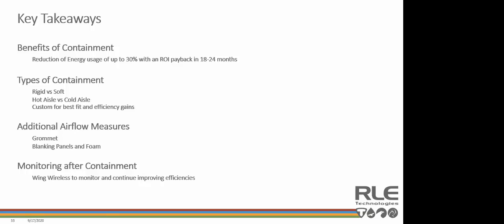Generally speaking, hot aisle containment tends to be a slightly better option. This is due to the fact that all warm air is directed back to the CRAC units in the most efficient way possible, which increases return air temperature and return air efficiency of the CRAC units. However, implementation can be difficult if the data center was not purpose-built from the beginning for hot aisle containment. Retrofitting an existing space with a return air ceiling plenum can be expensive, and the extra energy efficiency gain versus a cold aisle containment system might not be worth the additional expense.